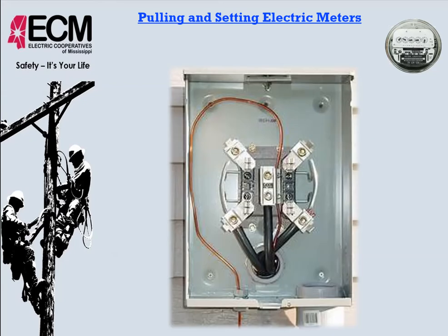Okay, now this one here's a mess. This one here is a mess. They've taken their wire and did a decent job of connecting here, keeping it from getting pulled out. But they've taken it and run it up to the top side, okay? And you're going to get your hots and your neutrals up here in the way of each other, okay? Then they've taken a bare wire and come off the bottom and gone to the inside. Okay? This is just the wrong way to do this. Your ground wire coming from your ground rod would need to come here. It can be bare. Make sure there's plenty of clearance between your load side that's going to be hot, and connect into there. Okay.